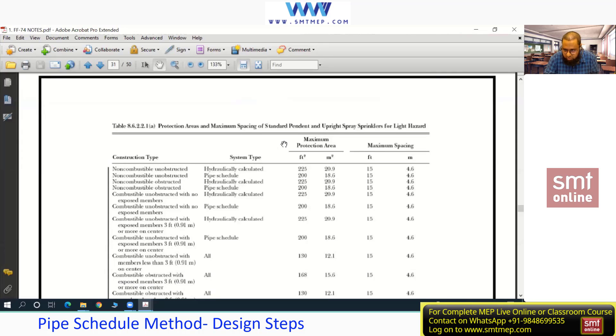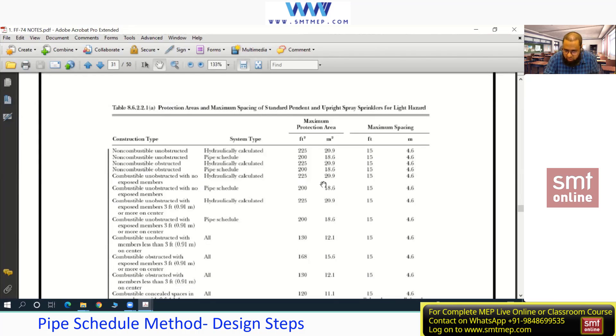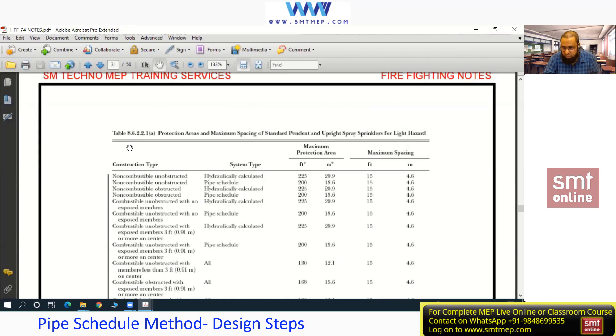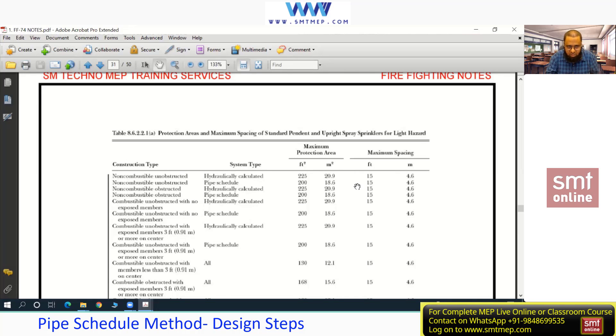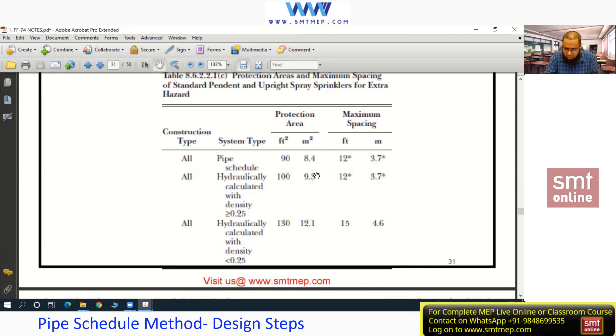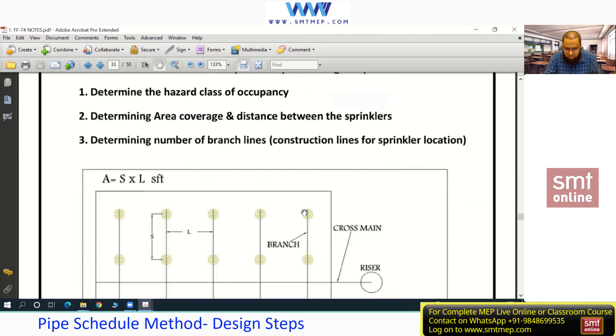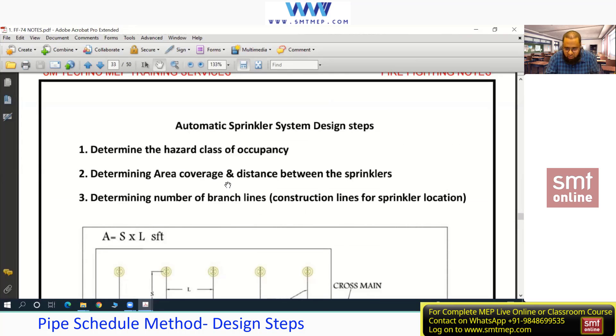In the 2019 edition, the values are the same — 225 square feet, 15 feet spacing — only the table reference number has changed. So once you know the hazard, you use this table to get the area coverage and distance between sprinklers. Step 3 is to determine the number of branch lines.